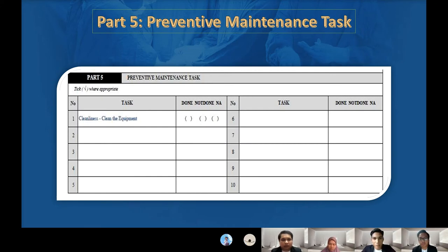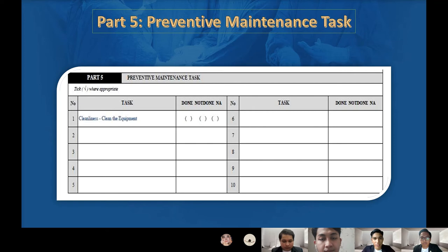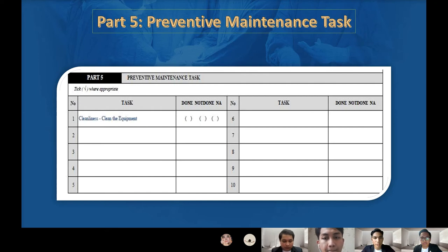For part five, preventive maintenance tasks: we need to check the cleanliness of the equipment. There are three available options: done, not done, and not available. For cleanliness, we inspect patient leads and coagulating and cutting tips for activity, cleanliness, and bits of tissue or carbon that would interfere with proper function. We also need to clean all electrical contacts.